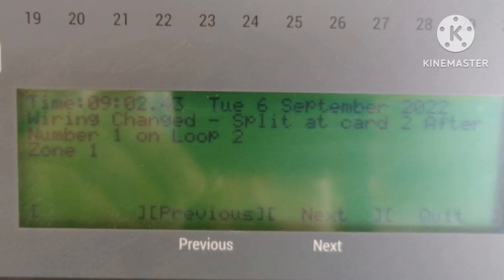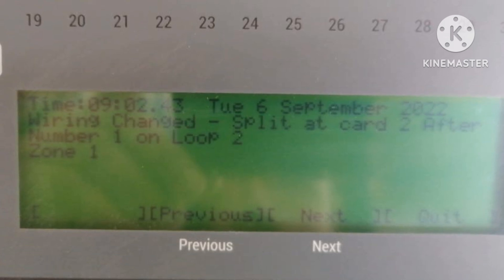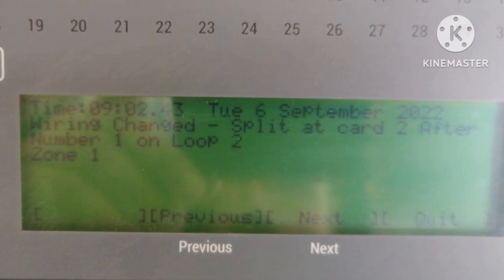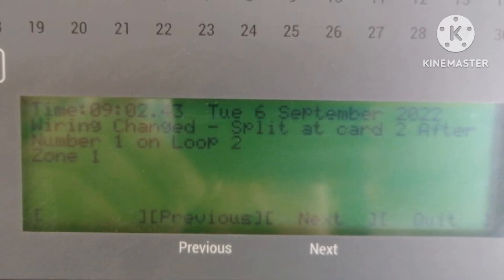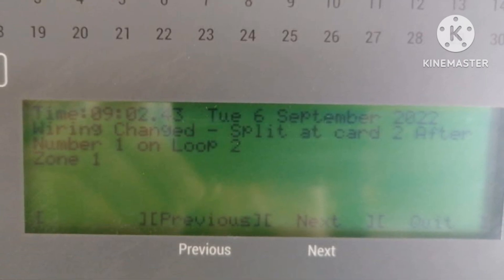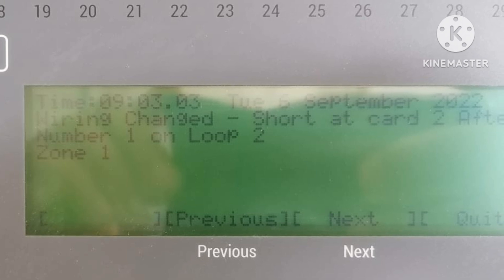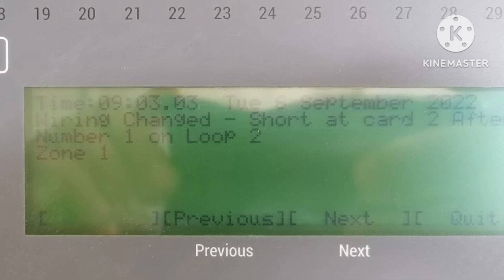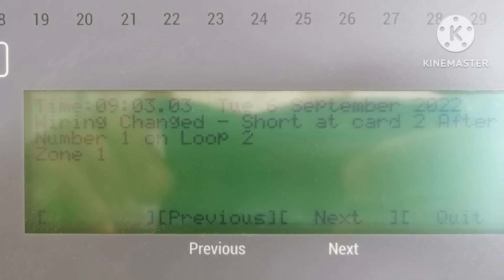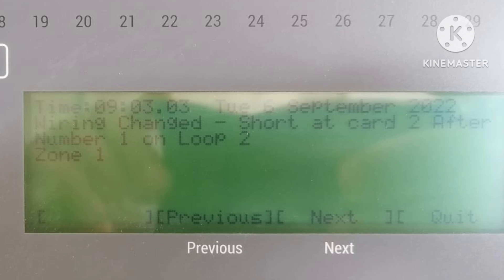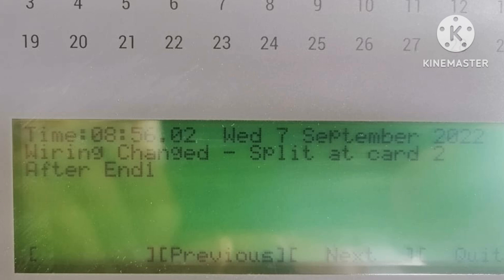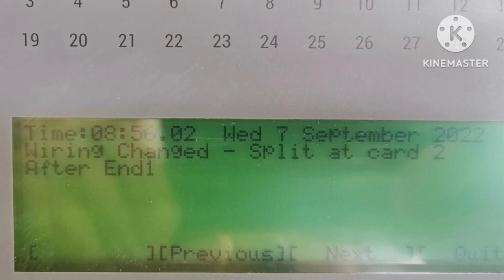This means your loop has been aborted, or is still being allocated or relocated. In this case we have to relocate the loop. But in some cases it is not relocated, because if there is a short — like a short on the card — you have to first fix the short. In case of a short, your loop allocation will not be completed.